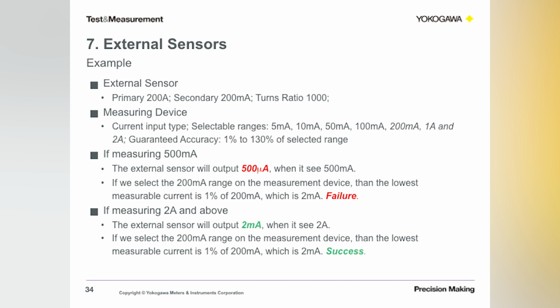Now, if you're expecting to measure 500 milliamp current using that external sensor, will the power analyzer be able to accurately measure that output signal? In this case, let's take a look. If you use the 200 milliamp range, the lowest the power analyzer can accurately measure is 2 milliamps, which is 1% of that selected range. But the sensor is going to output 500 microamps. So you see, this will result in an inaccurate measurement, right? Or even a failure. You may not be able to measure it at all.